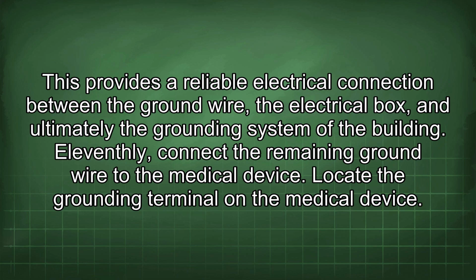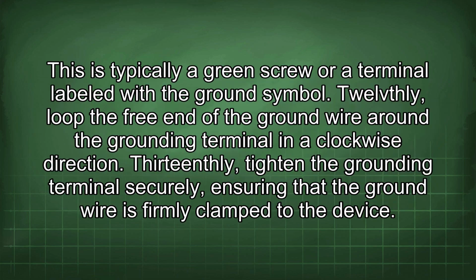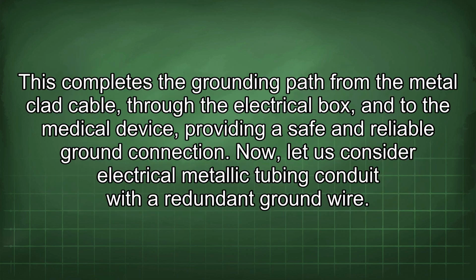Locate the grounding terminal on the medical device. This is typically a green screw or a terminal labeled with a ground symbol. 12thly, loop the free end of the ground wire around the grounding terminal in a clockwise direction. 13thly, tighten the grounding terminal securely, ensuring that the ground wire is firmly clamped to the device. This completes the grounding path from the metal-clad cable through the electrical box and to the medical device, providing a safe and reliable ground connection.